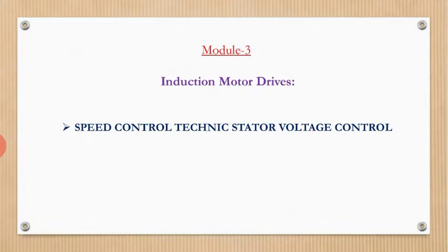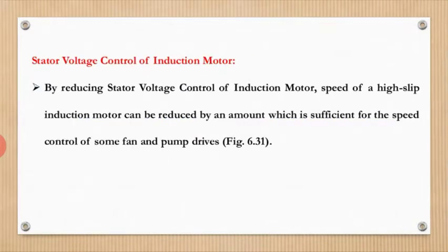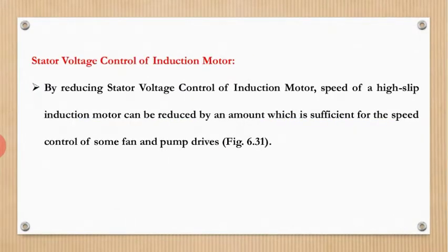So, today I am going to discuss the speed control technique, stator voltage control. Here the speed of an induction motor can be controlled by varying the stator voltage. By reducing the stator voltage of an induction motor, the speed of a high slip induction motor can be reduced by an amount which is sufficient for the speed control of some fan and pump drives.